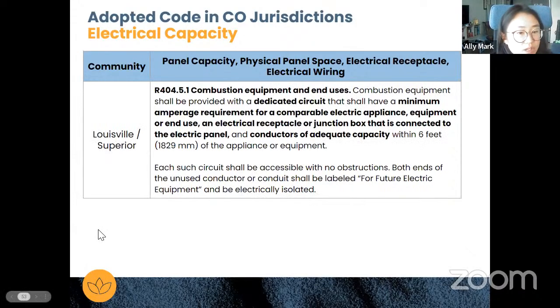And then one last one on electrical capacity. Louisville and Superior have the more open-ended version of this, which is combustion equipment shall be provided with a dedicated circuit that shall have a minimum amperage requirement for a comparable electric appliance, equipment, or end use, an electrical receptacle or junction box that is connected to the electrical panel, and conductors of adequate capacity within 6 feet of the appliance or equipment. Each such circuit shall be accessible with no obstructions. Both ends of the unused conductor or conduit shall be labeled for future electric equipment and be electrically isolated.